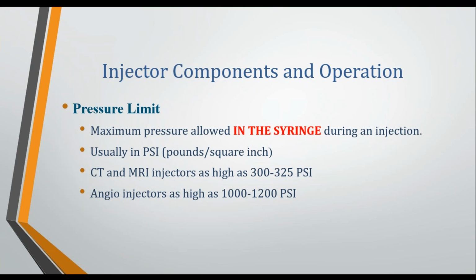You have to go back to your fluid dynamics and understand that when the fluid leaves the syringe, going from the large bore of the syringe to the very thin tubing coming out of it, that is where we get a dramatic exponential drop in pressure. In the syringe we would have, say, 1,000 psi. When that fluid gets out of the syringe and into the connector tubing, we are literally down to single-digit pressures, less than 10 psi. Here in the United States, the pressure is always measured in psi, pounds per square inch. A lot of injectors do give you the option to use kilopascals, kilograms, or even millimeters of mercury, but it's pretty much always measured in pounds per square inch.